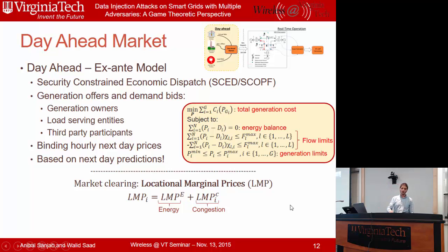However, what differs is how much each bus or each location in the system really affects the overall congestion in that system. What's the congestion? The congestion is almost a violation of the flow limits constraint, meaning that a line has reached its thermal limit, which means that no extra power can flow on that line anymore. So this line is mainly blocked. No additional power can flow, meaning that if we have two regions in the system, and one region has cheap power, like from renewables or from nuclear, that needs to reach a load on the other side, it cannot do that anymore because no additional power can flow, and hence this barrier needs to be penalized in some way, or not always penalized, but it needs to be accounted for.